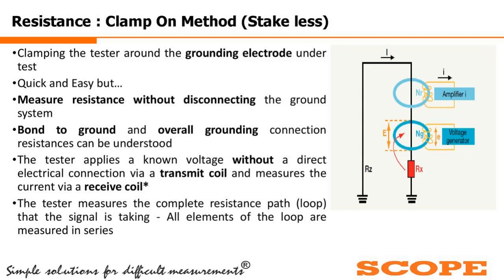Now, first is the clamp-on method, or stakeless: clamping the tester around the ground electrode under test. So directly I will be putting the clamp onto the earthing strip or earthing path of the installation. This is quick and easy, a very quick, simple one. With a current tong kind of a setup, or clamp-on setup, I have to use it, and immediately I will be getting the result. So easy also, quick result, but there are so many buts coming. What are the buts, ifs and buts?